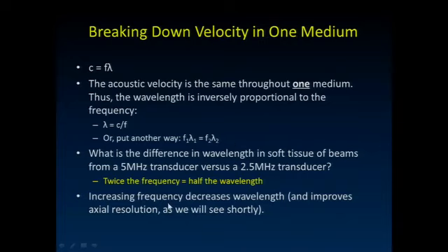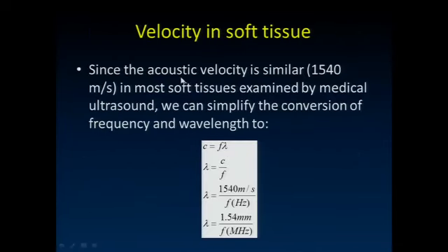We like using the highest frequency possible because that really gives us the best axial resolution, the best resolution along the direction that the ultrasound beam is propagating. The problem that we'll see as we go a little deeper is the higher the frequency we go, the more the sound beam is attenuated as it goes into the material. So it really restricts how deep we're able to image into the tissues there.